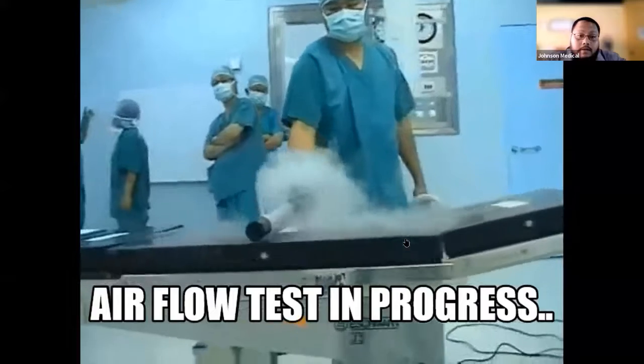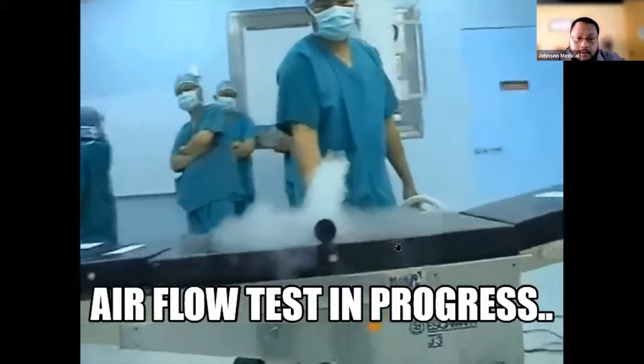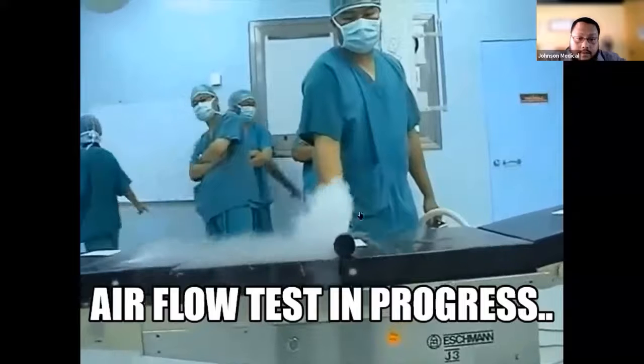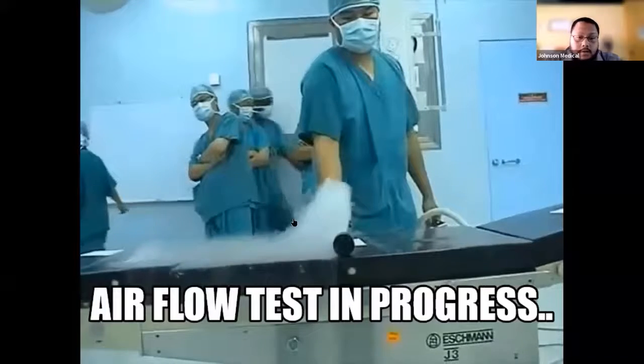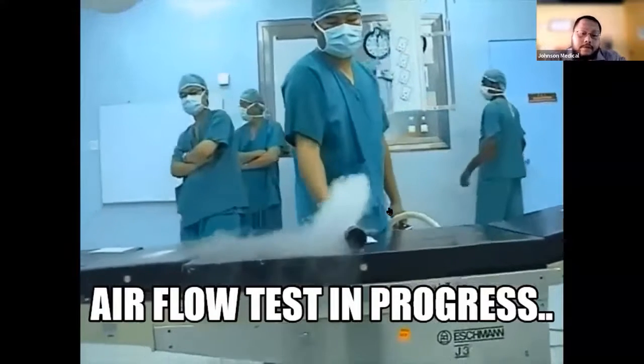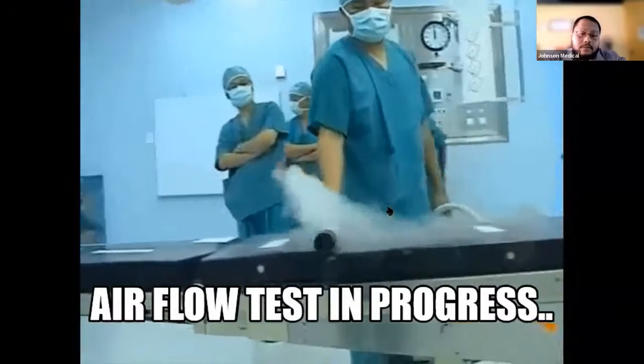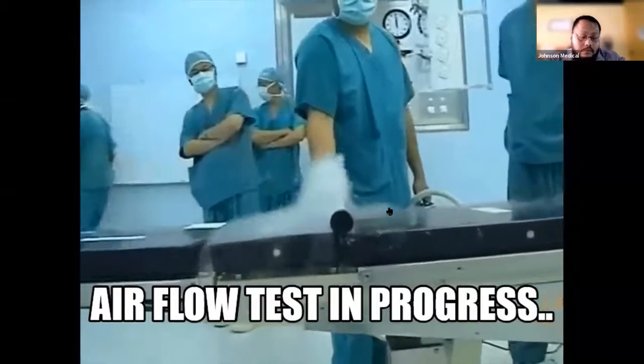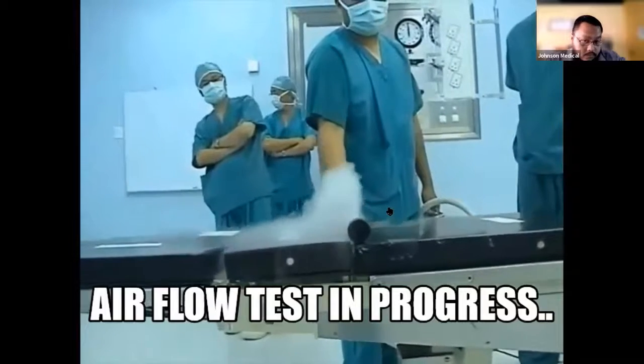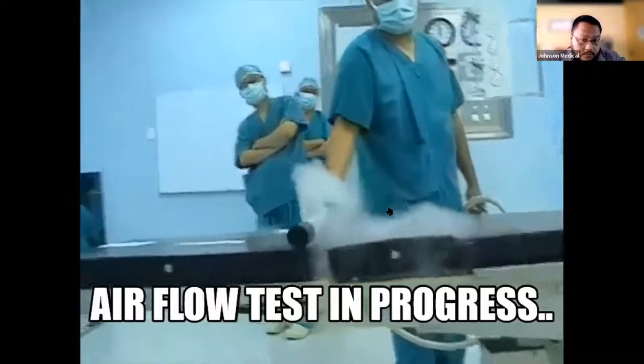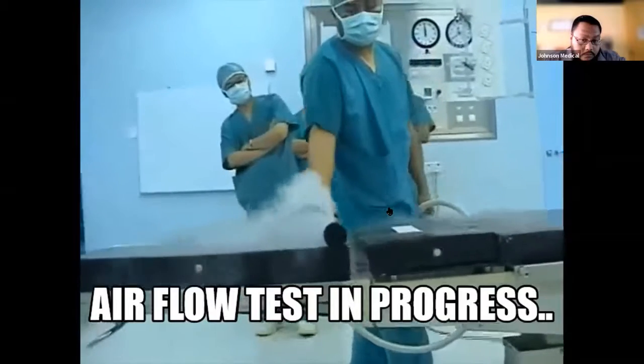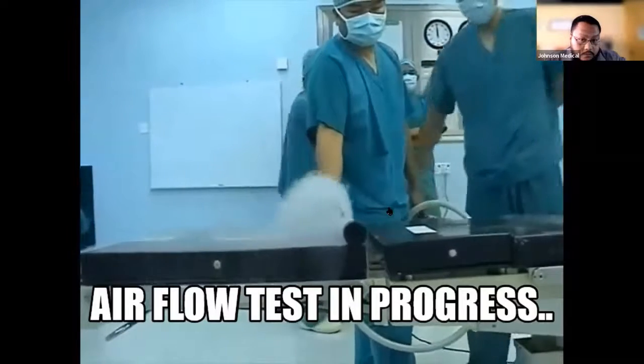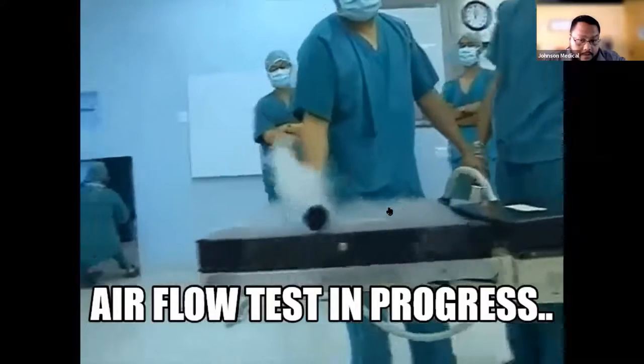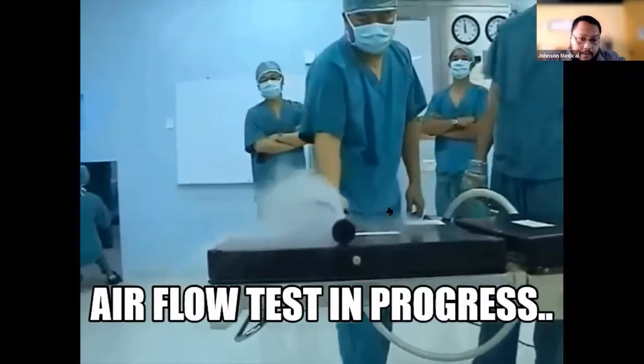And here you can see how the clean air is pushing all the dirty air towards the exhaust, which will be on the left side of the video. So you can see not much recirculating air going back to the surgical area.